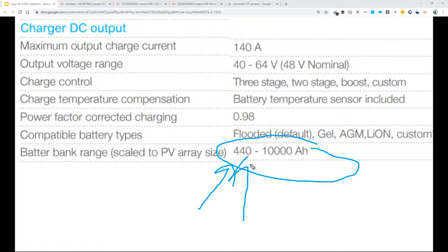So there is in the spec sheet a number that they say this is the smallest amount of battery storage we recommend you have. But it really depends on the battery chemistry. And for entry level lithium ion, you're looking at 2.5 times the output capacity of the inverter should be the minimum battery bank size.